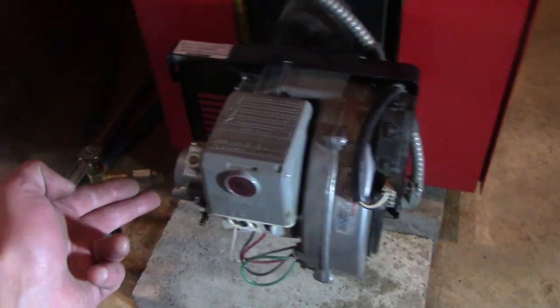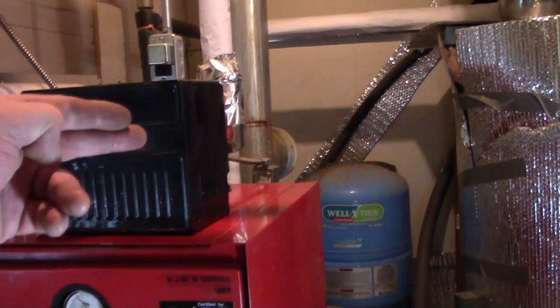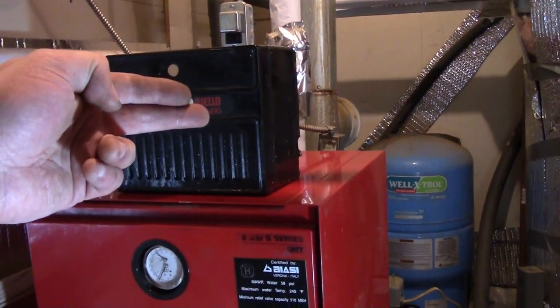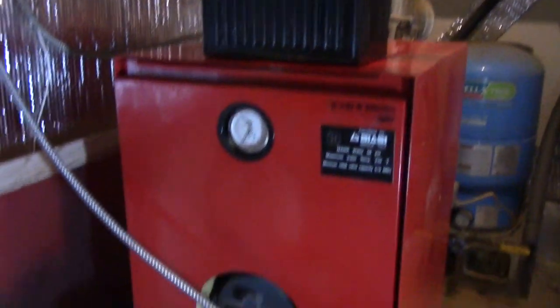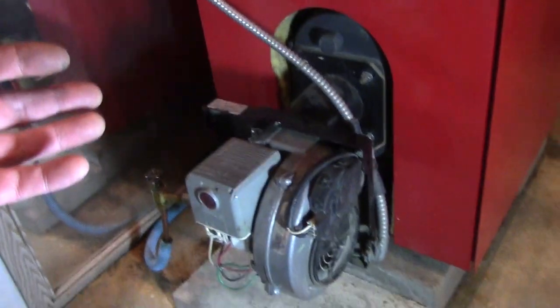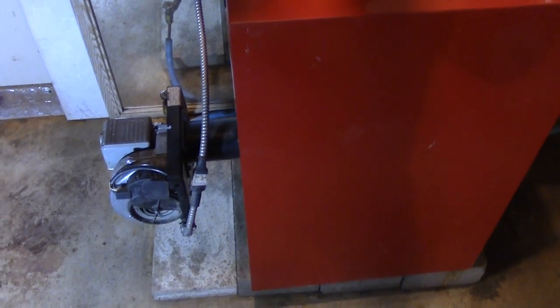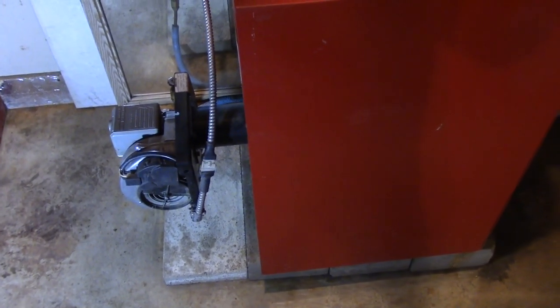A couple of things we aren't able to address in this video series yet — without the proper tools — would be the pump pressure, which I mentioned when we did the pump screen. We should also check the flue gases, which I don't have a tool for, and commonly they'd test the stack temperature as well. Hopefully that fills the gap, Dan. If there are other things, put them in the comments below and I'll try to address them. Give me a thumbs up if you found it helpful and hit subscribe. I do have a boiler cleaning video coming up, so stay tuned — that'll probably be the last one in the series.